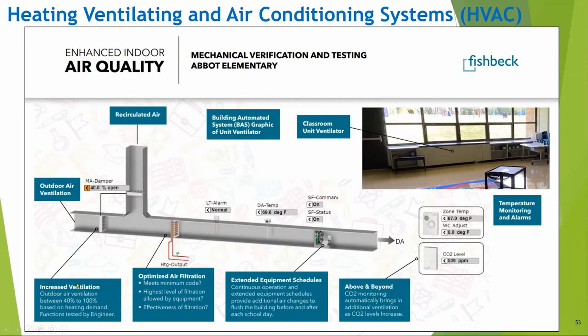So they're looking at how much increased ventilation can we provide, and depending on the piece of equipment, and that, again, it's tied to outside temperature, 40 to 100% outside air provision. They're looking at the filters. We're also developing extended equipment schedules. So we'll be operating the equipment 2 hours prior to occupancy and 2 hours after occupancy to be sure we're really flushing the buildings out.